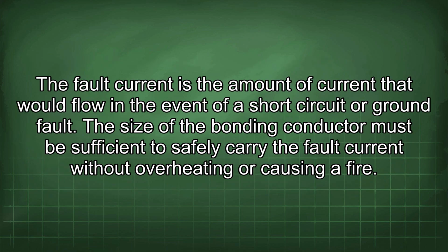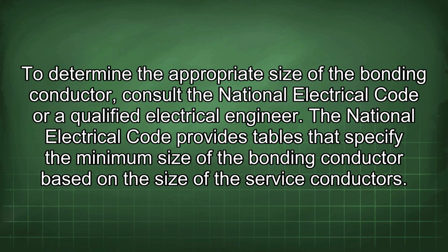The fault current is the amount of current that would flow in the event of a short circuit or ground fault. The size of the bonding conductor must be sufficient to safely carry the fault current without overheating or causing a fire. To determine the appropriate size of the bonding conductor, consult the National Electrical Code or a qualified electrical engineer. The National Electrical Code provides tables that specify the minimum size of the bonding conductor based on the size of the service conductors.